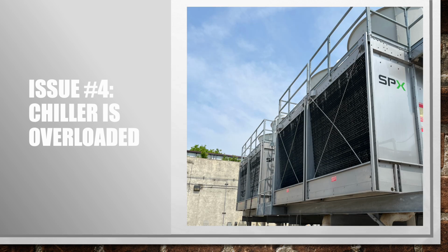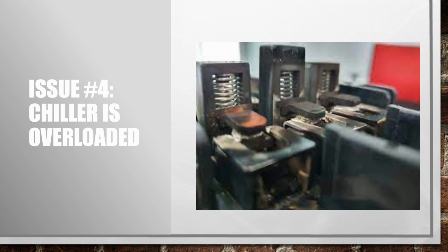You could have an issue with your cooling tower. Maybe it's not sending cold enough condenser water back to the machine. If the condenser water temp entering the machine is very high, you're also going to have very high head pressure because of that, and it's also going to overload the machine. I do have some other videos that break down diagnosing an overloaded machine. So if you think that this is the problem, go check those out and they should be able to help you out a lot more.